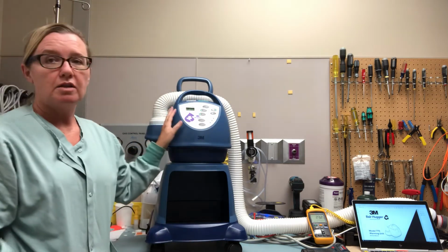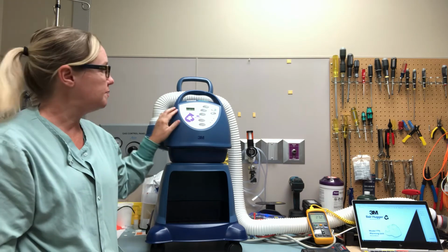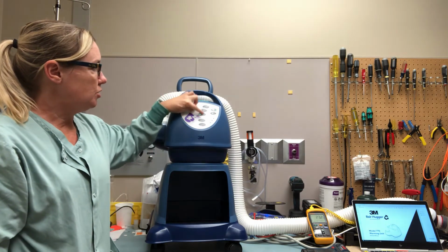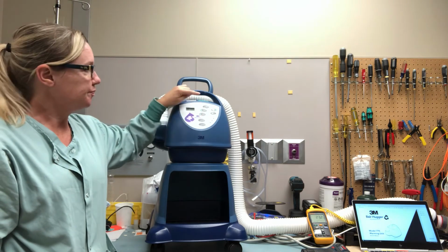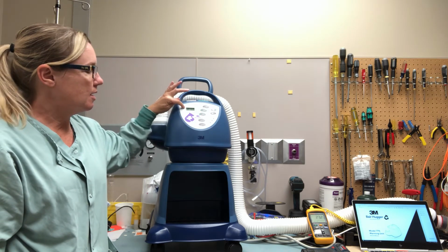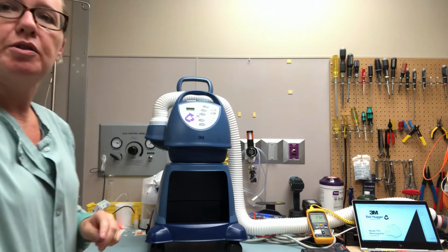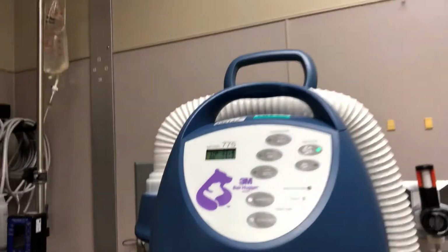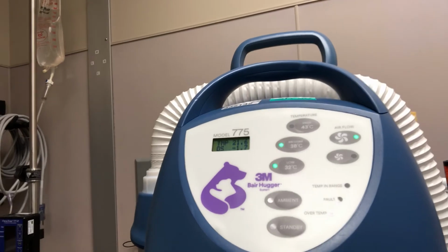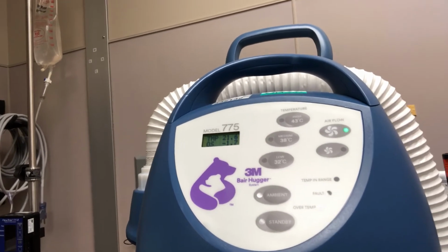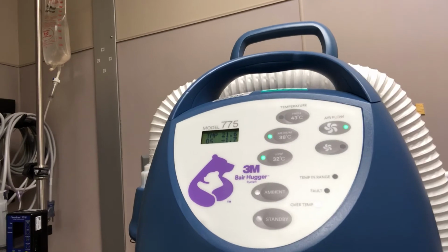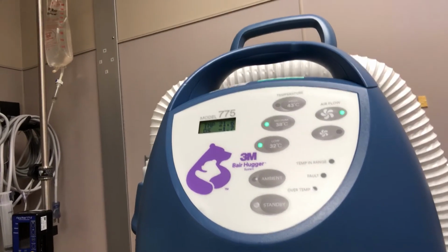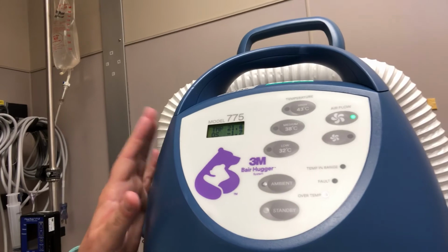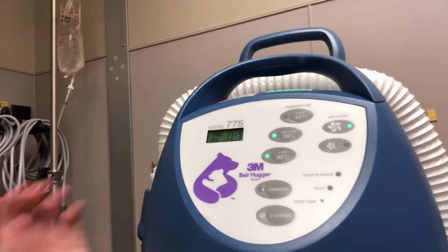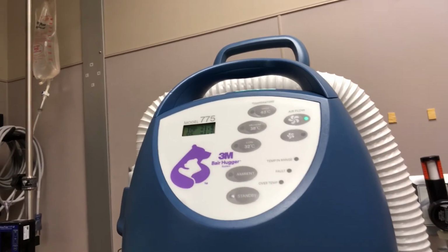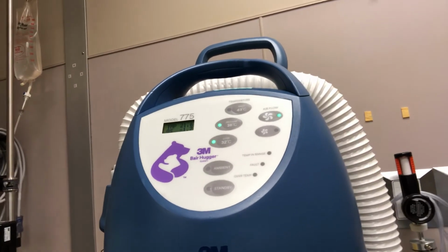Okay, so now we're in the calibration mode. These 2 LEDs are blinking, and up here I can see that my temperature is 21.6 and my offset is minus 1.7. So this lets us change the temperature reading on the Bair Hugger to match what our calibrated thermometer at the hose end says.